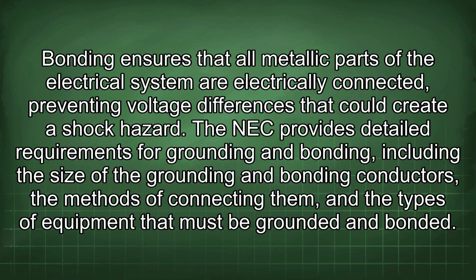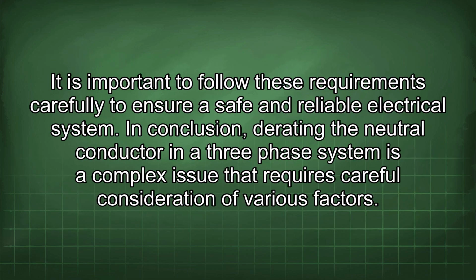Bonding ensures that all metallic parts of the electrical system are electrically connected, preventing voltage differences that could create a shock hazard. The NEC provides detailed requirements for grounding and bonding, including the size of the grounding and bonding conductors, the methods of connecting them, and the types of equipment that must be grounded and bonded. It is important to follow these requirements carefully to ensure a safe and reliable electrical system.